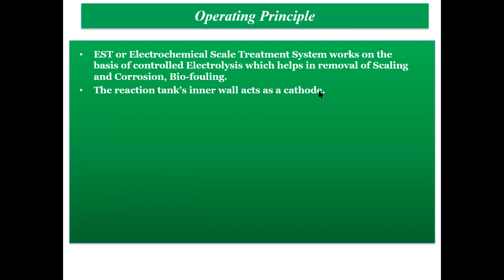Now we'll come to the operating principle of an EST system. As the name suggests, electrochemical scale treatment system, this treatment basically works on the principle of electrolysis and helps us in removal of scaling, corrosion, and biofouling. By electrolysis, we obviously know that there will be some anode, some cathode, and some connecting fluid between them, which we call the electrolyte. In our case, the tank inner wall acts as the cathode, and those red ones in the pictures I showed in the previous slide are the anodes. The anodes are basically made of titanium nickel oxide so that they are highly resistant to the water.